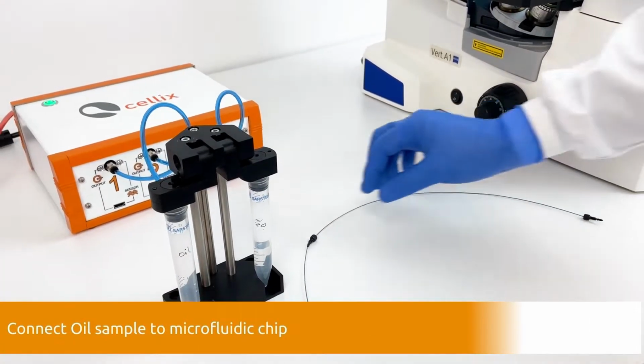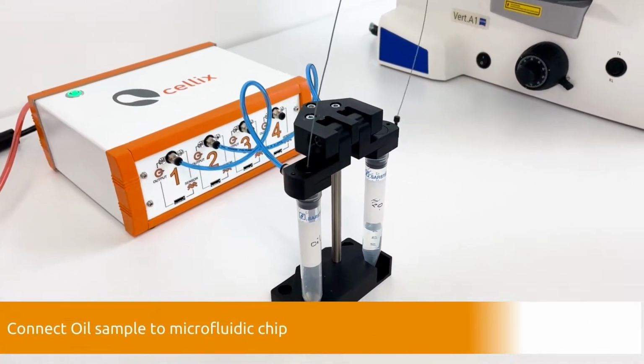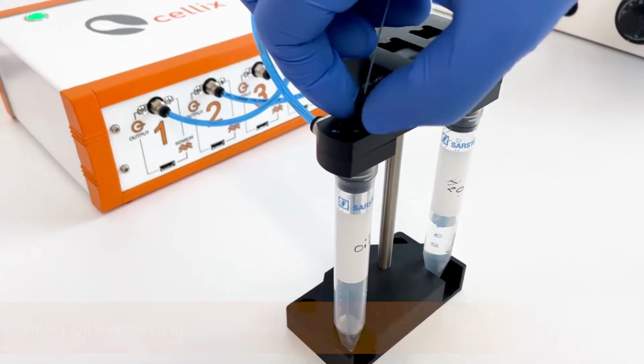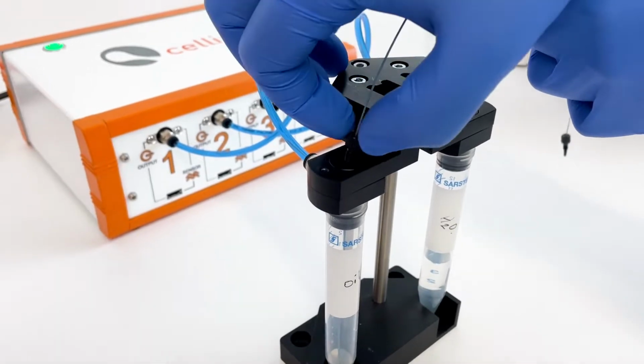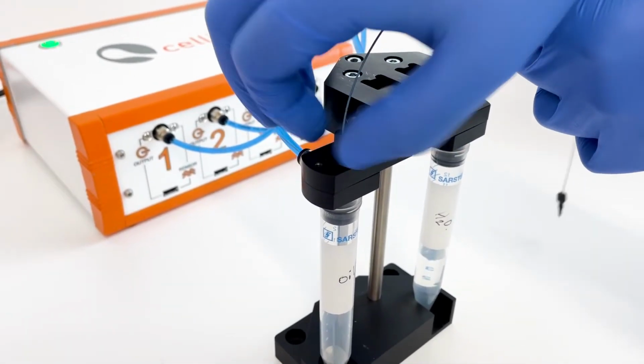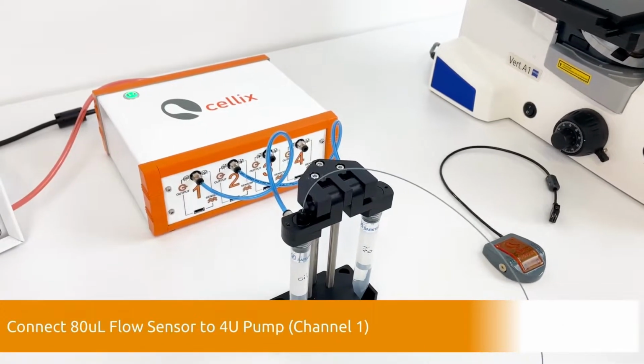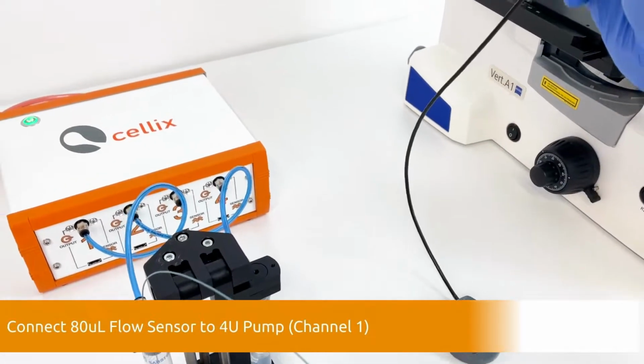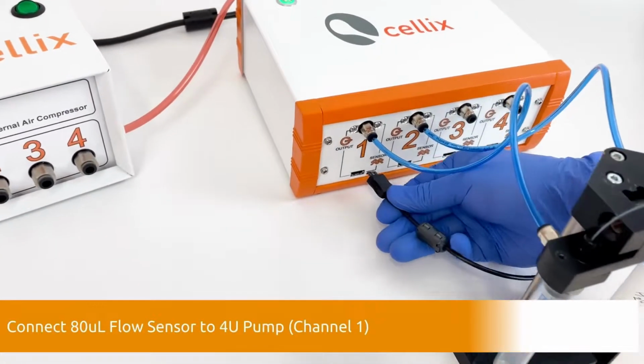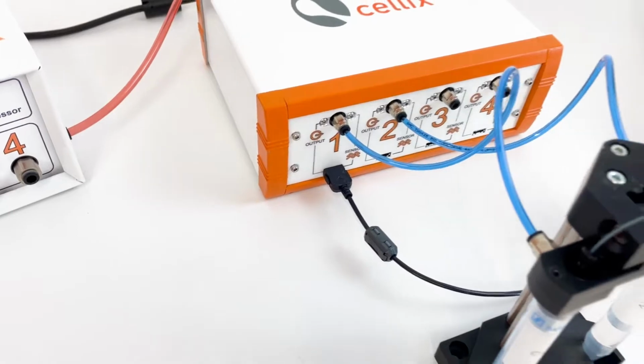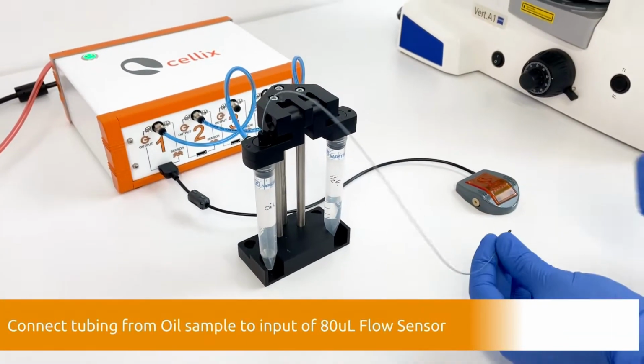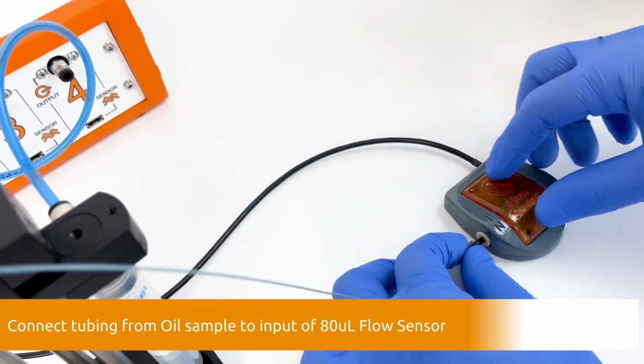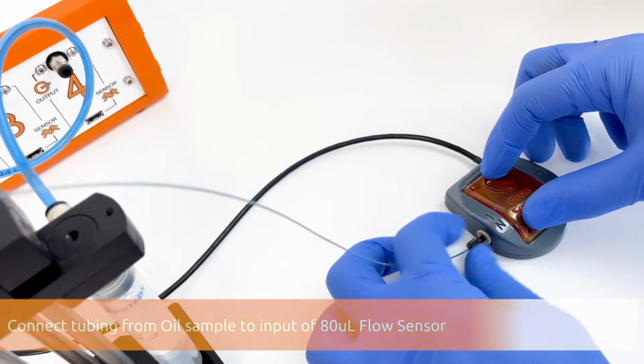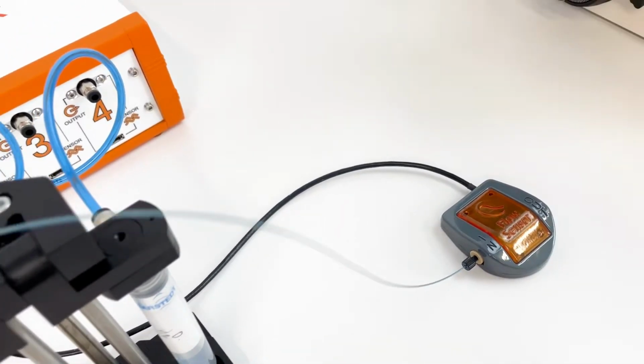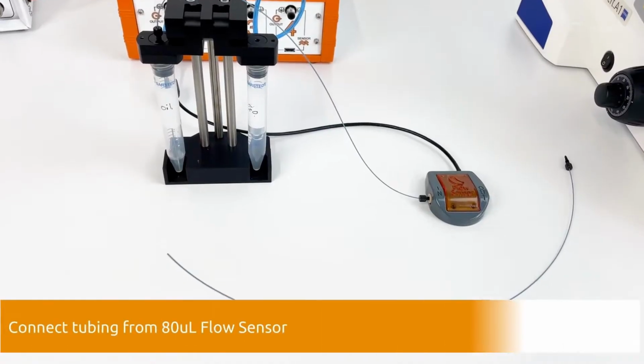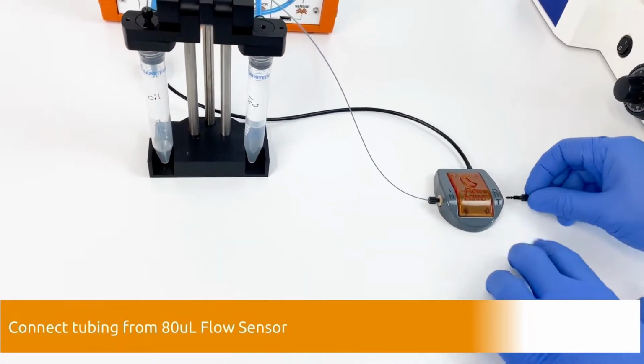To connect the oil sample to the microfluidic chip, first connect the blue PEEK tubing to the oil sample tube. Connect the 80 microliter flow sensor to the 4U pump channel 1. Then connect the tubing from the oil sample tube to the input of the 80 microliter flow sensor. Finally, connect the blue PEEK tubing to the outlet of the 80 microliter flow sensor.